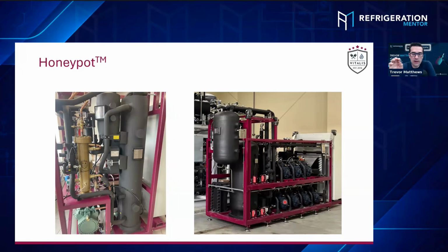And one of the things is, when Jonas's team designs a system, and whoever designs a system, there's an amount of oil that needs to be in that system. They send that to you. They tell you how much oil this system should take, depending on how much pipe run there is and the size of that reservoir, because the oil has to go around and lubricate everything as it travels through. So you just want to understand that there is guidance. It's not like you just go and add a bunch of oil and then figure it out. There is a strategy behind that from the manufacturer and the designer. So always go back to the legend of the unit, which usually says how many liters or how many gallons it should take.